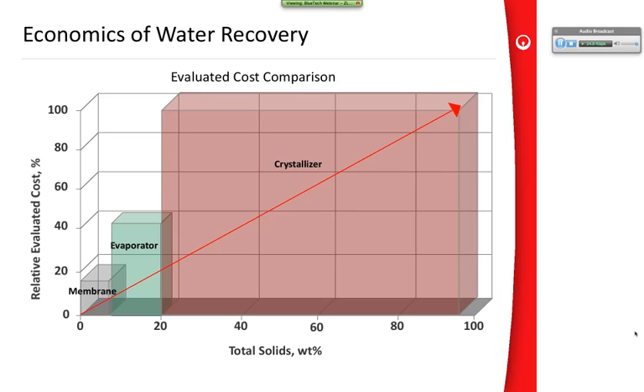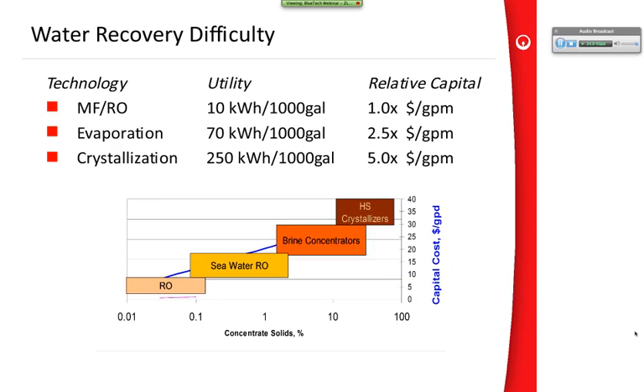As for the economics, this will give you a relative idea. Membrane systems are generally made of plastic and concentrate the brine up to a fairly low concentration, about 4 to 6%. Evaporators tend to be more expensive because they go to a higher concentration and also have more metallurgy requirements. Crystallizers, going to dryness, have the highest cost of all, but they do the least amount of water removal - so even though the cost is quite high, the evaporation rate is quite low. I think these numbers are in line with what Mike presented earlier: the energy requirements and capital costs for RO are relatively low compared to evaporators, and of course compared to crystallizers.